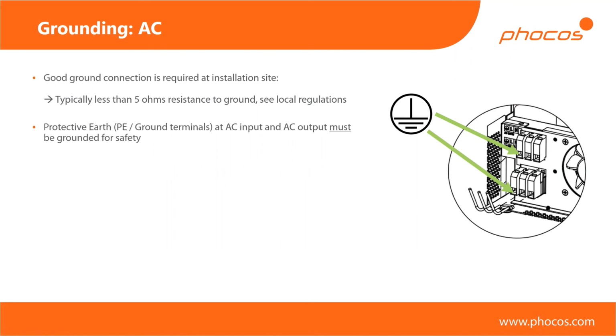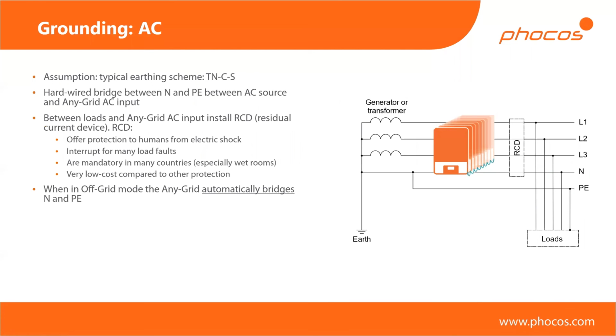And you need to make sure that you have a low impedance ground at your area of installation. Then typically, and this really depends on your country, what kind of a grounding scheme you have. So I'm looking at TNCS here, which is common, I think, in most parts of the world, certainly is in Europe.